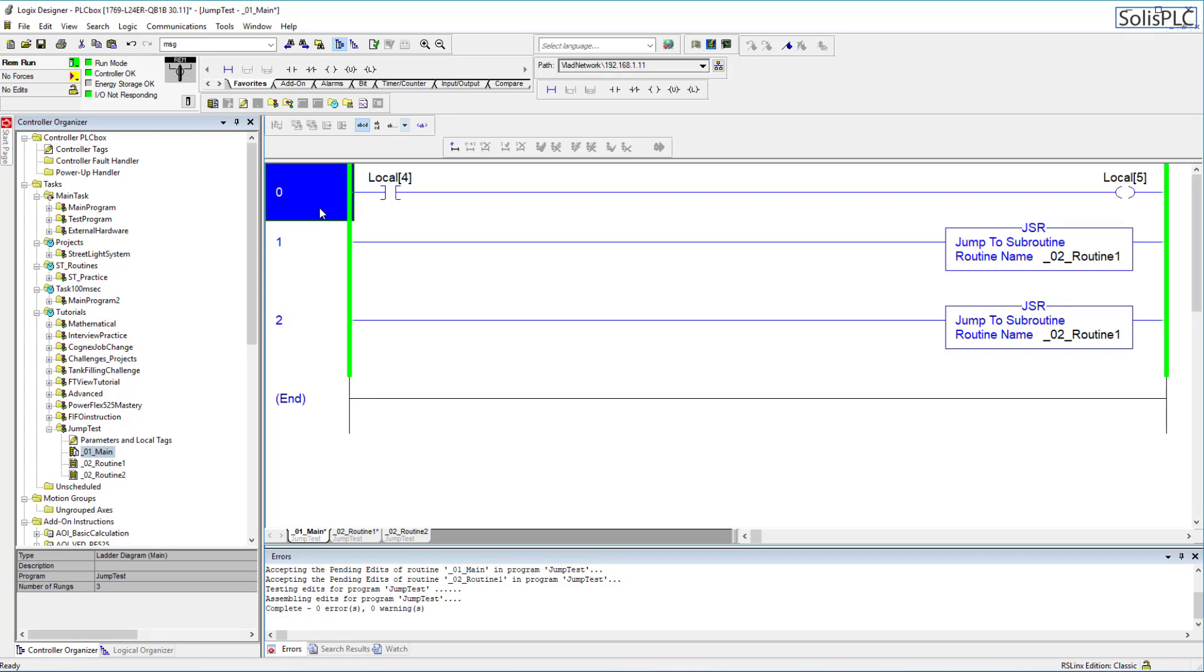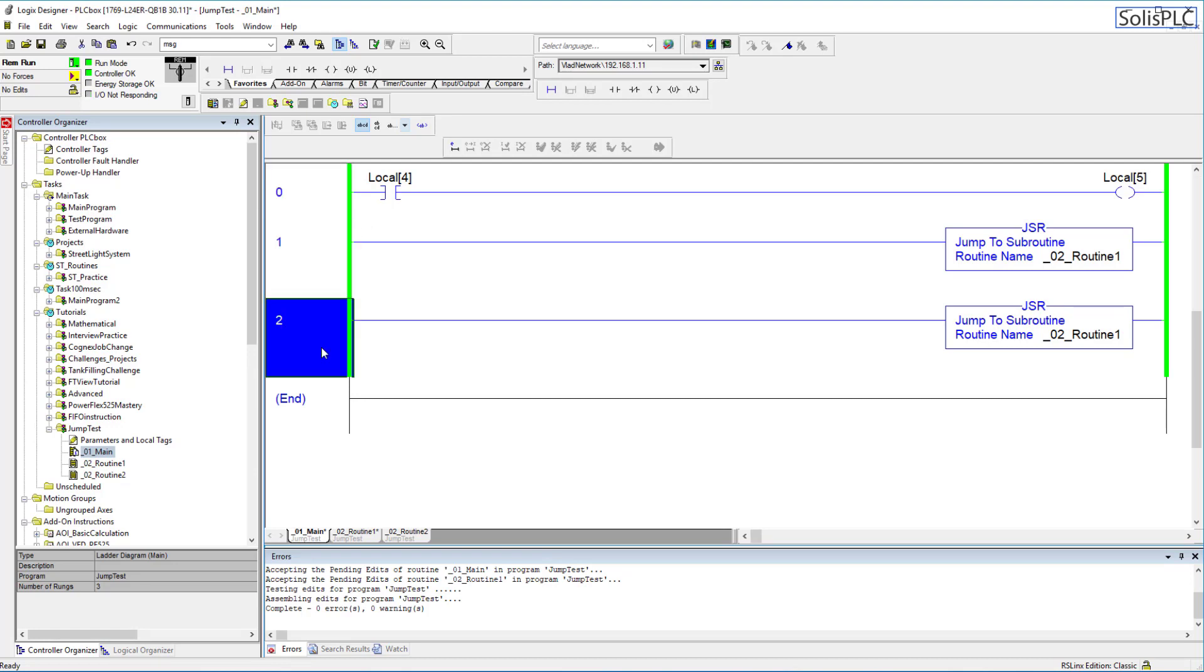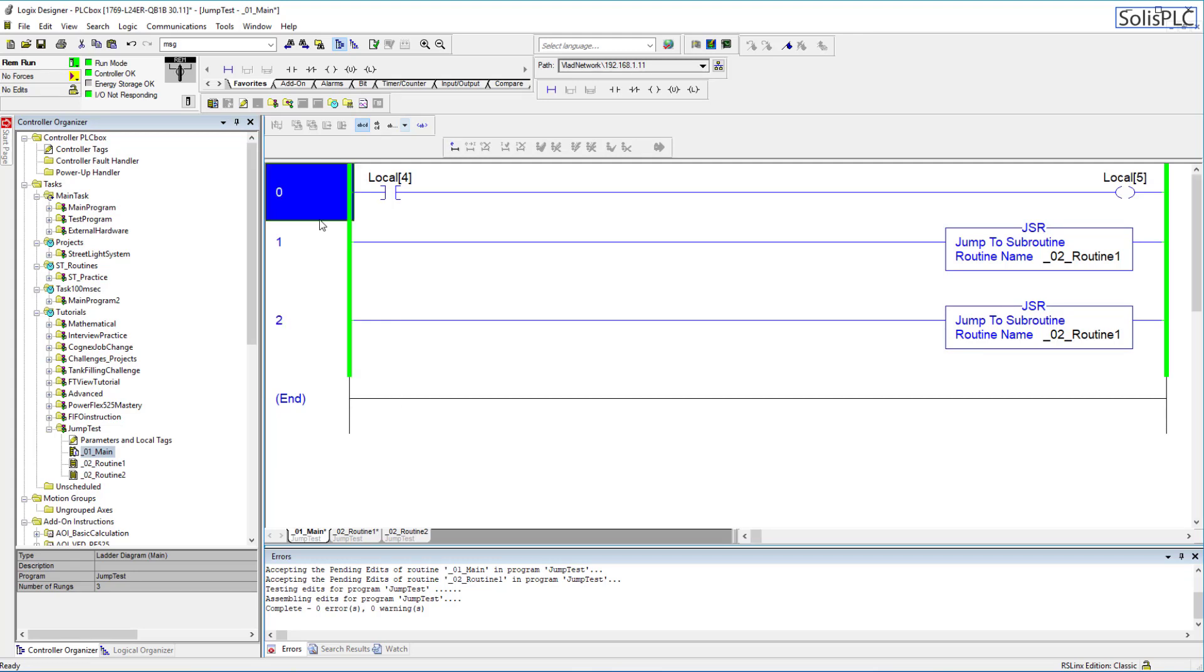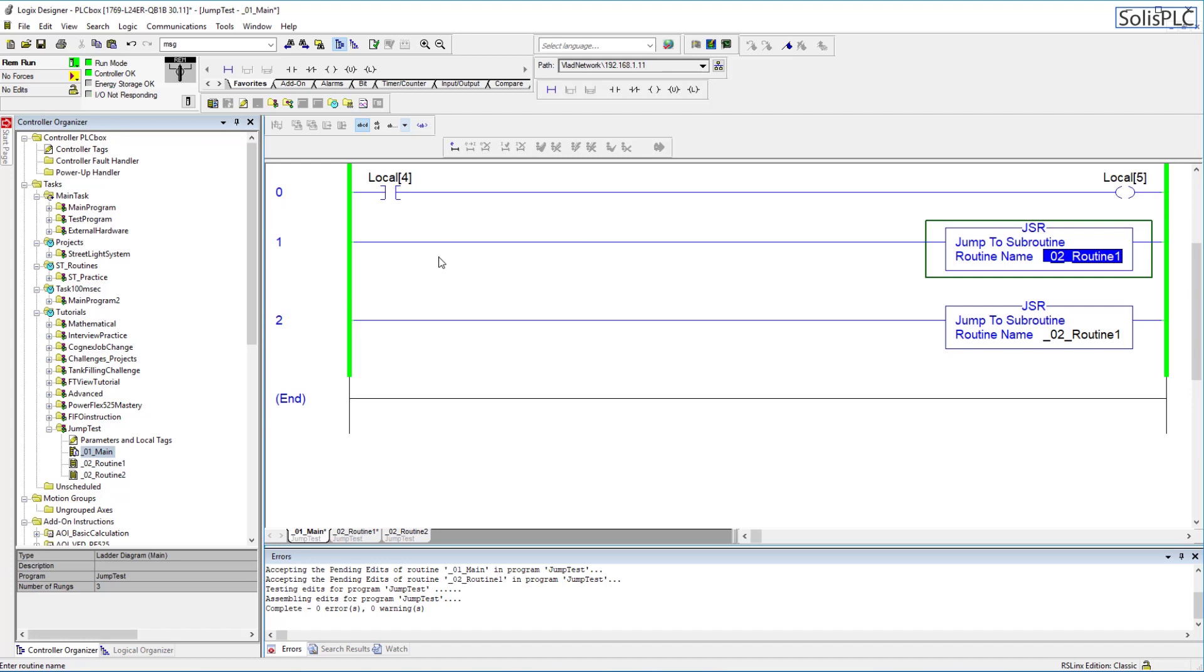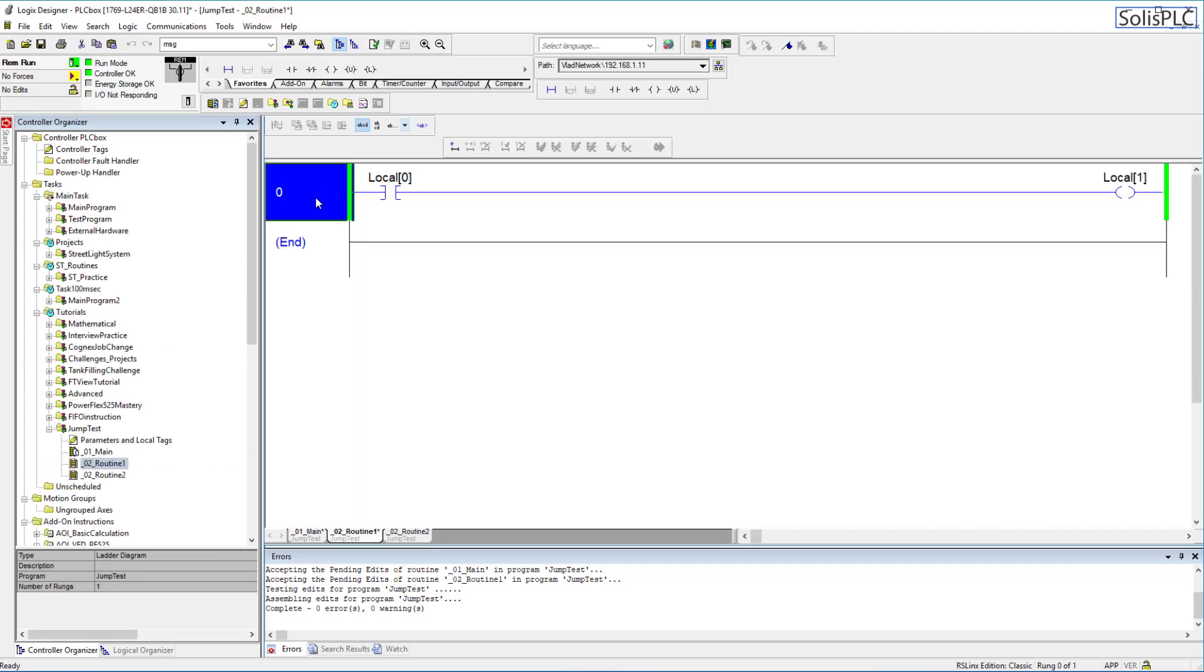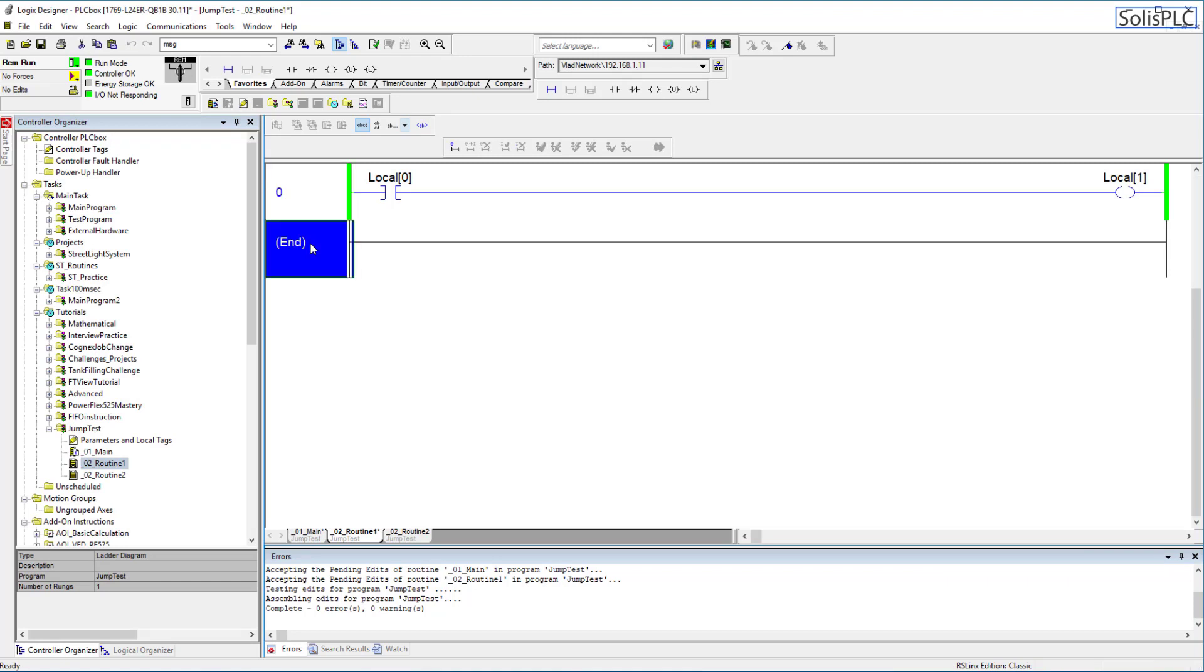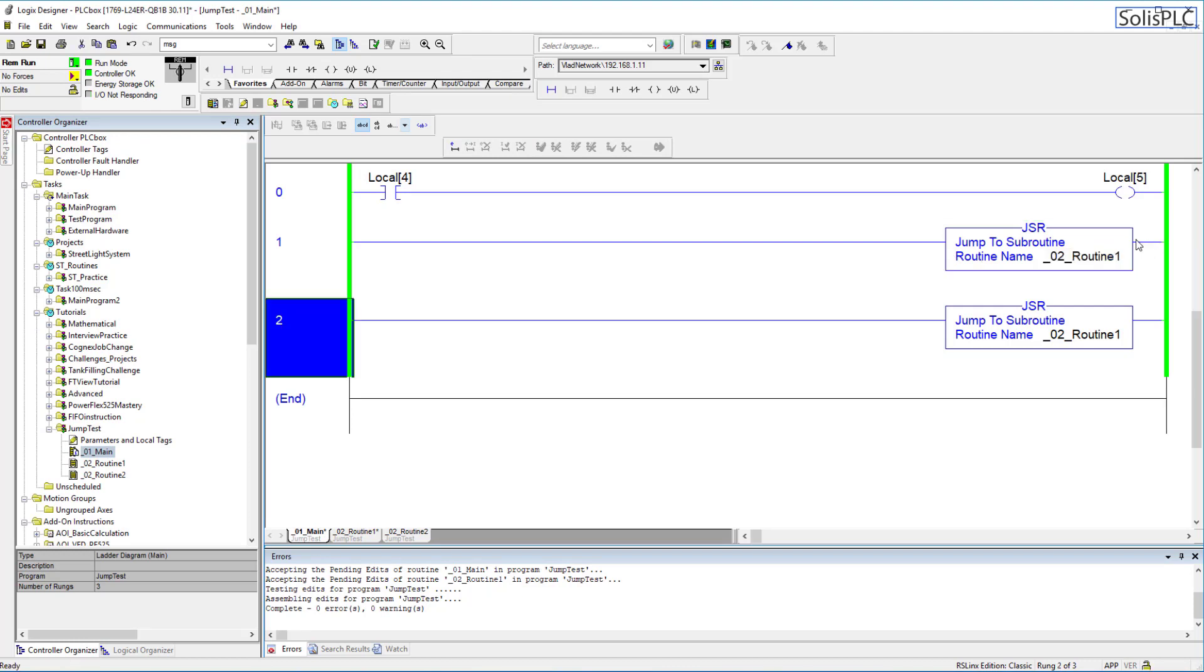Now as I've mentioned a couple of times the PLC is going to execute everything sequentially. So the first rung that's going to be executed is going to be rung 0 then rung 1 rung 2 and then of course it's going to repeat back to 0. Now in case of a JSR instruction what's going to happen is as soon as the PLC reaches rung 1 it's going to scan across and see this JSR. It's going to jump to the routine which is underscore zero two underscore one. It's going to flip to the logic which we have here. It's going to execute rung 0 then it's going to come to the end and it's going to jump back to where the JSR was completing this rung and then go into the next rung.